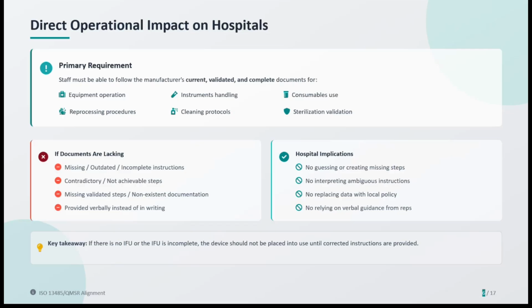Ultimately, staff must be able to follow current, validated, and complete manufacturer documentation for ordering, handling, reprocessing, storage, and use. If the IFU is missing, incomplete, contradictory, or not achievable, the device should not be placed into use. And if it's already in circulation, it must be removed from use until a compliant IFU is obtained. That includes devices being used for the first time in the US market. The correct response is not to figure it out locally, but to stop, then escalate to the manufacturer and at times to the FDA, and then obtain validated instructions before using the device again.